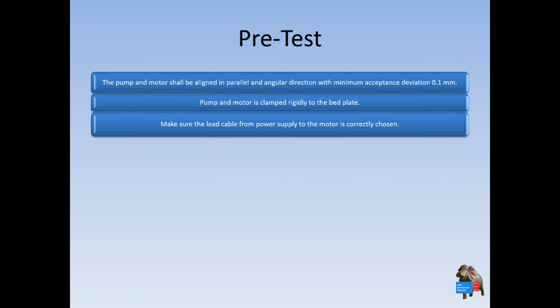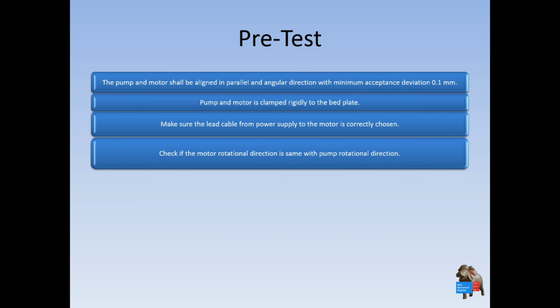And then you have to make sure the cables from the motor connected to your control panel are correctly chosen and correctly tightened. Next, you have to ensure the correct rotational direction of the pump, because when you connect the cables, you may find that the direction is incorrect, and you need to modify it to the correct direction. You have to look at the pump. Usually there is an arrow on the body of the pump showing the correct direction of the pump.